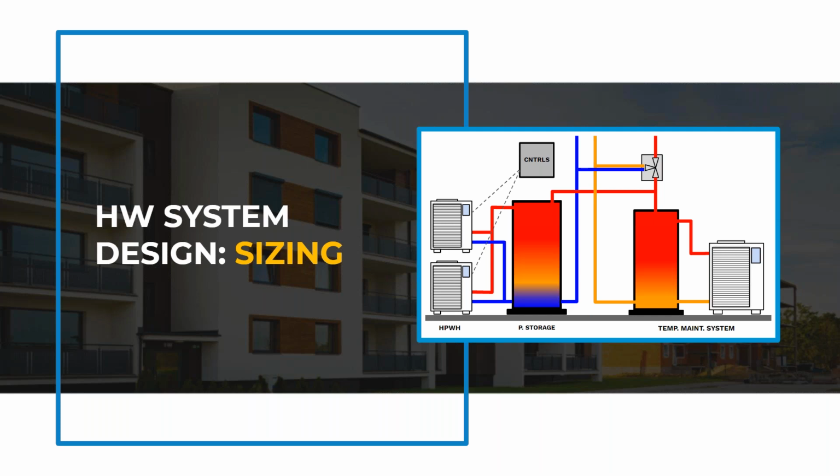Yeah, so if we can stop that pump, that helps. And the longer we can stop that pump, the more it reduces the associated losses because we're not circulating water during that period. However, in most multifamily buildings, people want hot water at all hours.